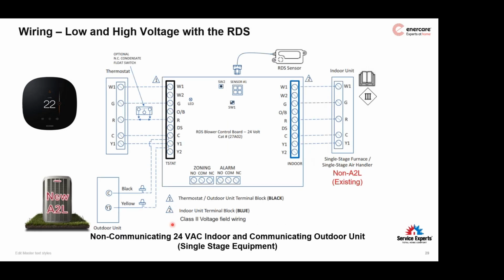And then finally, just a standard 24-volt connection, single or 2-wire out to the outdoor unit. So this would be a non-communicating outdoor A2L piece of equipment paired up with an older legacy system that is non-A2L compliant. Same 24-volt system, single stage heat, single stage cool. Again, much like the communicating system, this is one of the more simplified wiring setups, but probably very common in what we do day to day.